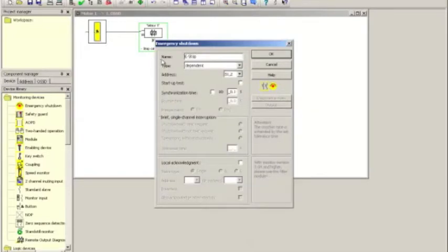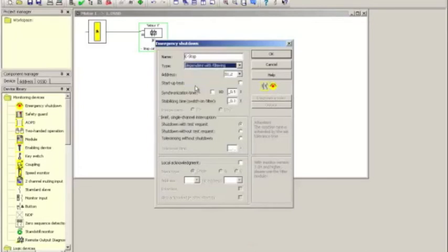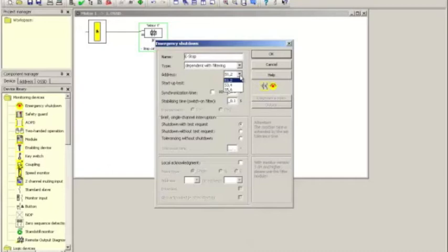Call it e-stop. And we select dependent with filtering to allow for a little bit of bounce and synchronization or asynchronicity between two contacts. And out of the three sets that are available, I have connected this e-stop to the contact set labeled S1, S2, so I make sure I select that. That's all I need from here.